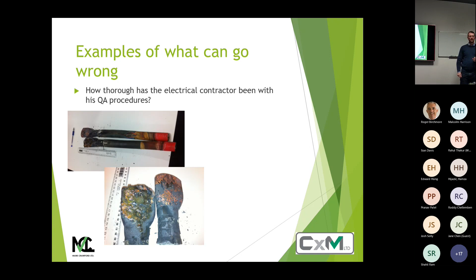But this was very, very close to burning the whole building down because, I'll show you some more. There you go, there's the terminals, and then they've actually welded the bolts. How hot must that have got? That one on the left there is what it should have looked like. So quite a difference. So that's through bad QA systems. Somebody has used the wrong bolts, they've used the wrong washers, they haven't tightened them up properly, no one's checked it. They've probably hand tightened them up.